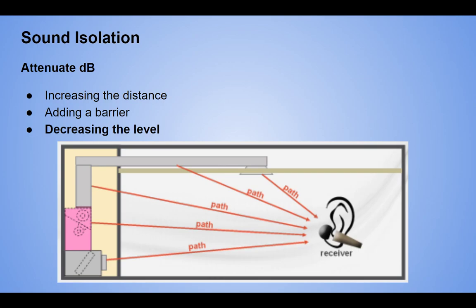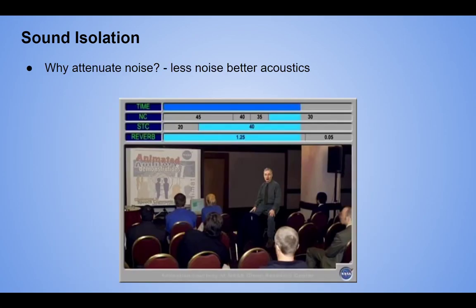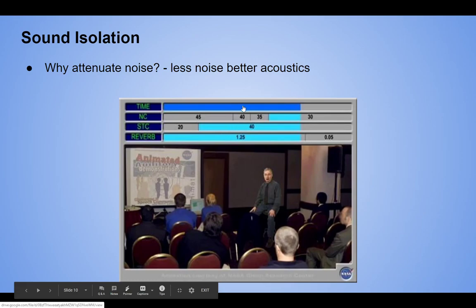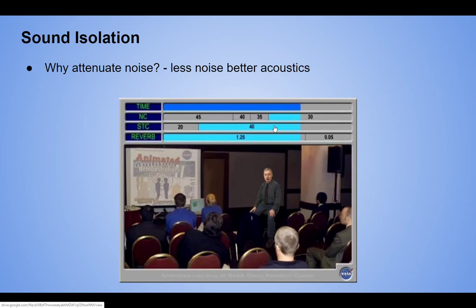Plan around this: put transitional spaces or non-critical acoustic spaces between noise-producing spaces and acoustically sensitive spaces — increase that distance. Attenuating the noise gives us better acoustics. As you decrease background noise, the lecture becomes clearer. The clearest condition is lowest background noise, highest STC, and lowest reverberation time — more of the direct sound. But STC from 20 to 45 matters: if you move to NC30 background in a dead room, you'd definitely hear that bouncing ball.